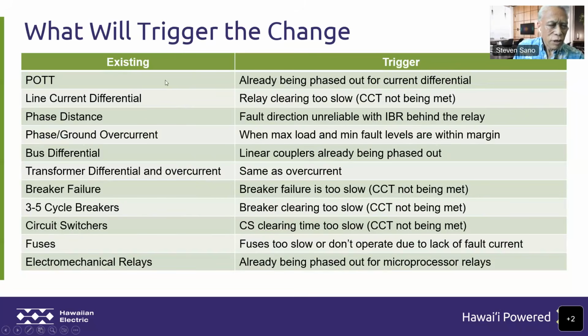Things like POTT, our current high-speed transmission line protection scheme, we're already seeing issues, so that's being phased out rather to current differential. Whenever we put in a new IBR-based generation plant, lines around the plant are converted to current differential if they are not already current differential. Current differential for transmission lines, again, it's a speed issue. We think current differential itself is fairly robust, fairly reliable, but the speed may not be sufficient, so we might have to change that out to traveling wave. And again, it's the critical clearing time not being met by existing line current differential. Phase distance, again, it's the unreliability of that scheme with inverter-based generation near to it.